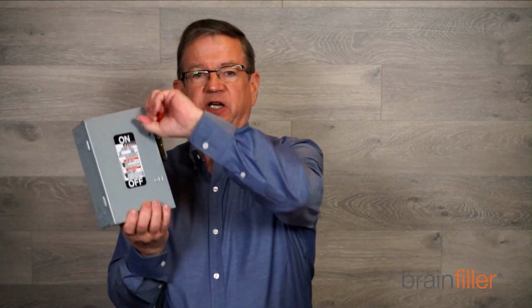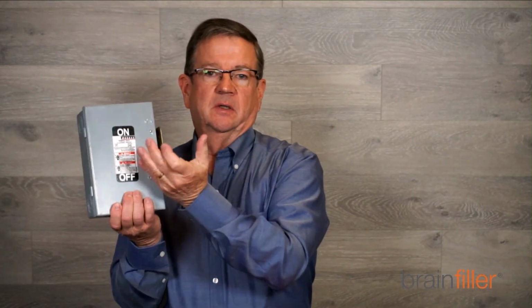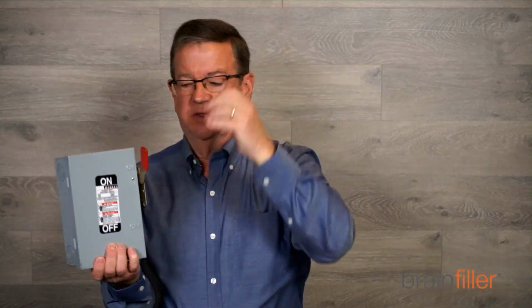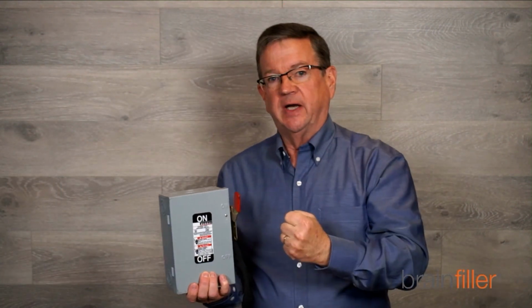Is an arc flash possible when switching a 480 volt switch to the off position versus turning it back on? That's more of a probability thing. So I think the question is, this isn't 480, but the question is, is an arc flash possible doing this compared to this? Typically, energizing is considered to be a little more hazardous than de-energizing because you don't know what you're closing into. Did something happen downstream?